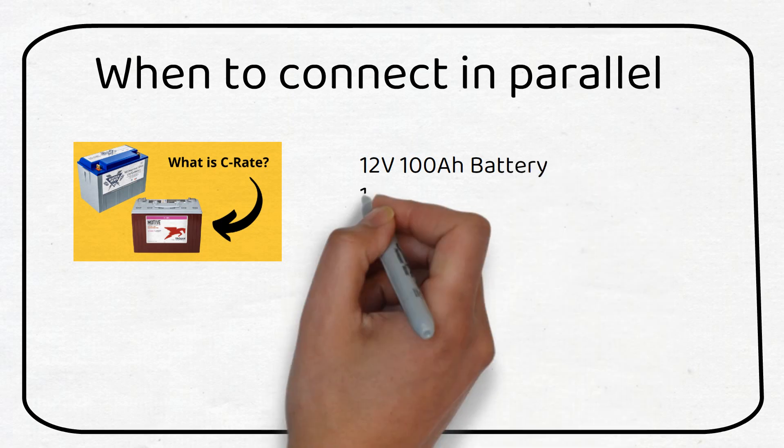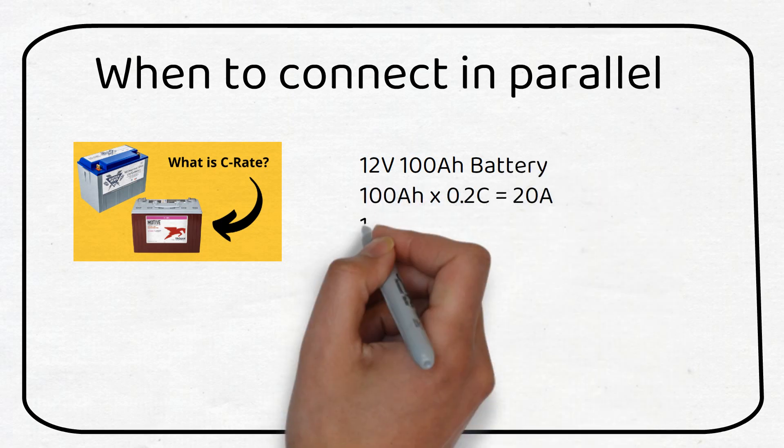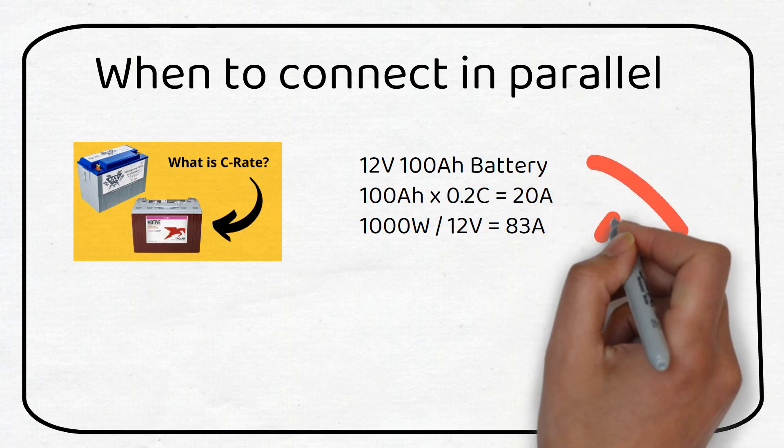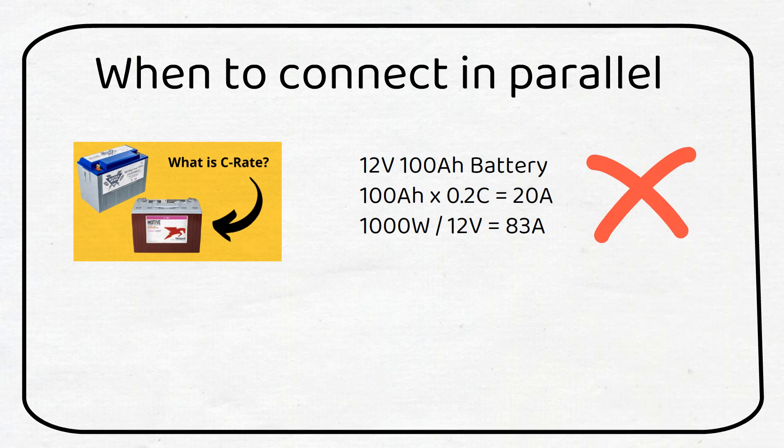Let's say you have a lead acid battery that is 12 volts, 100 amp hours and you have a 1000 watt inverter. The C-rate of a lead acid battery is 0.2C or in this case 20 amps. To feed your inverter you will draw about 83 amps. This is much more than the recommended 20 amp charge and discharge rate. While the system might work it will reduce the lifespan and the capacity of the battery due to heat generation.